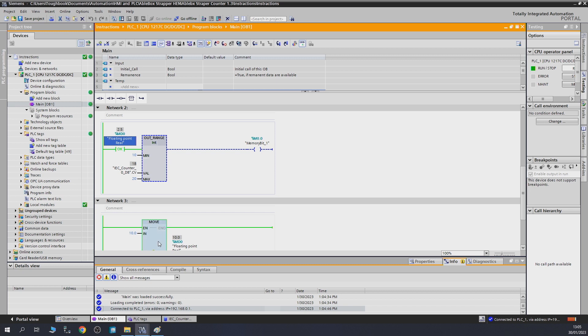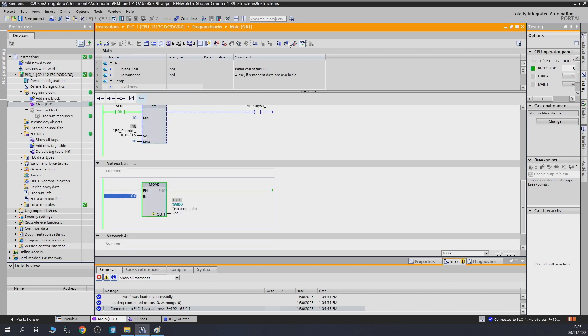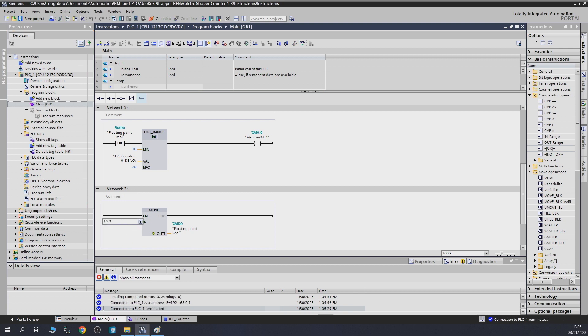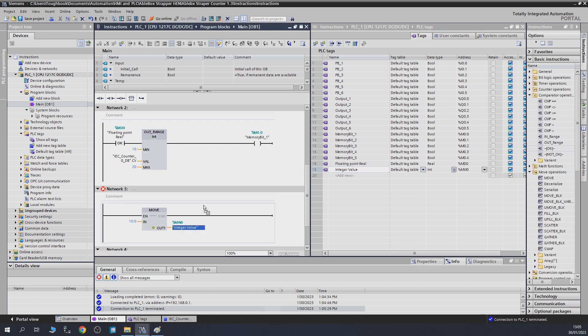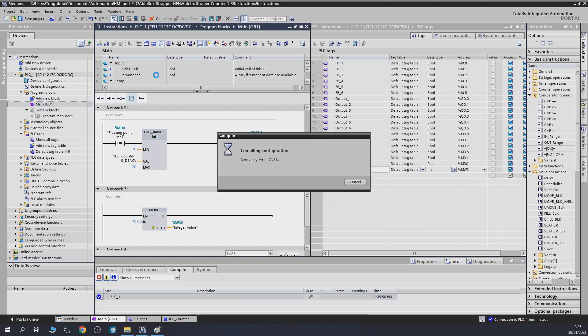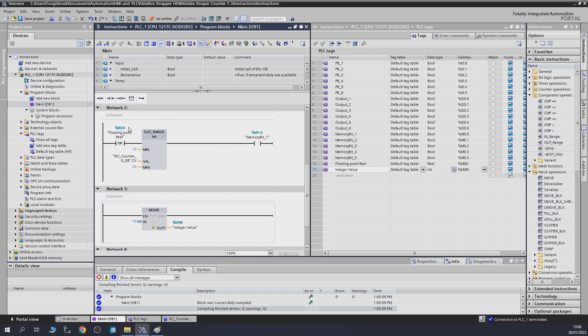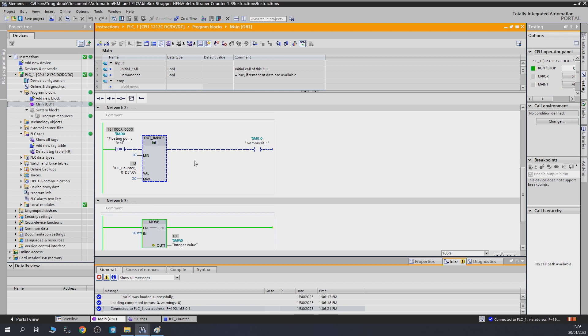To illustrate what could go wrong, we'll break the code by changing the data type from real to integer and changing the word type accordingly. Now something has gone wrong — there's a very weird value appearing in MD0. The Check Validity block says that's no longer a valid floating-point number and blocks the signal. Whoever programmed it will need to investigate. This shows why Check Validity is very useful.